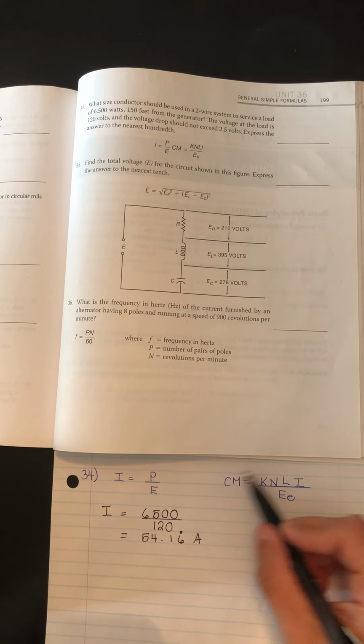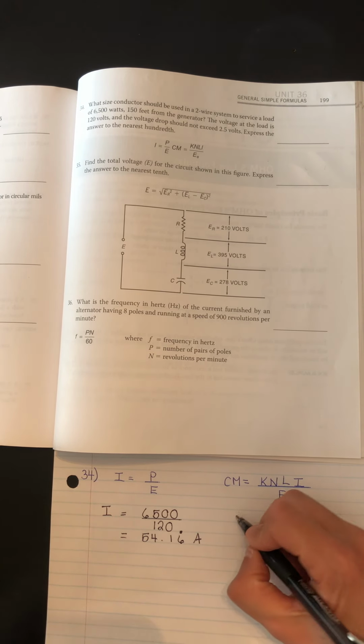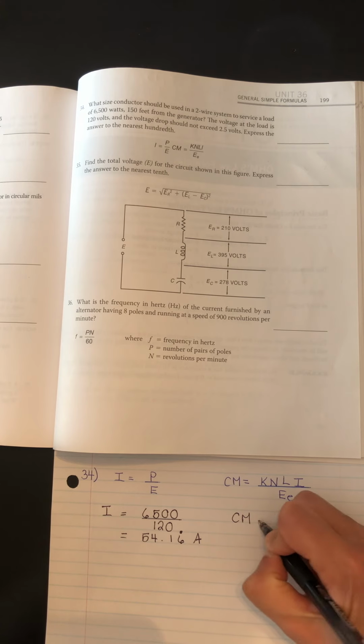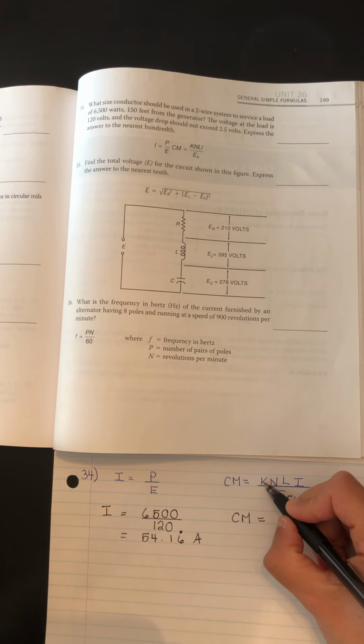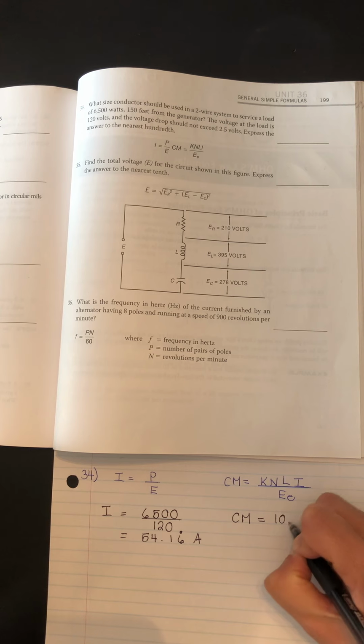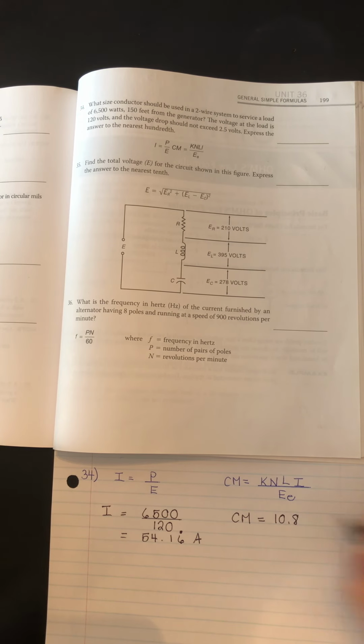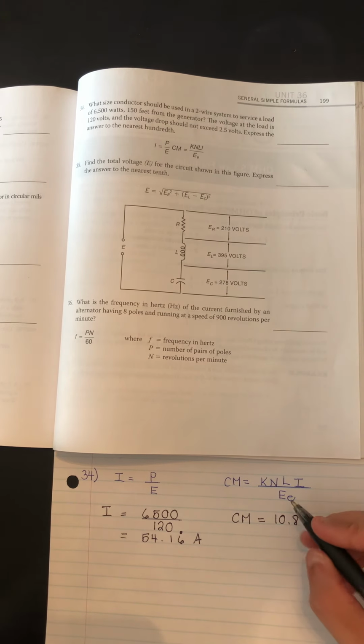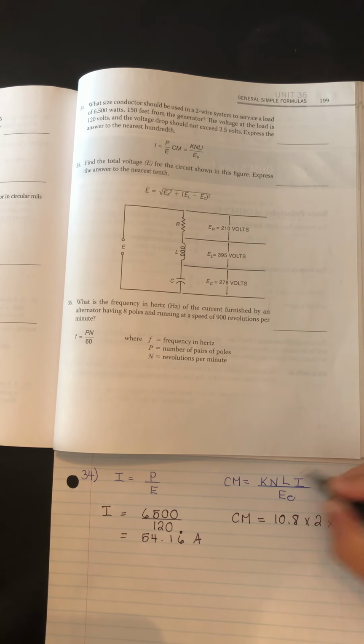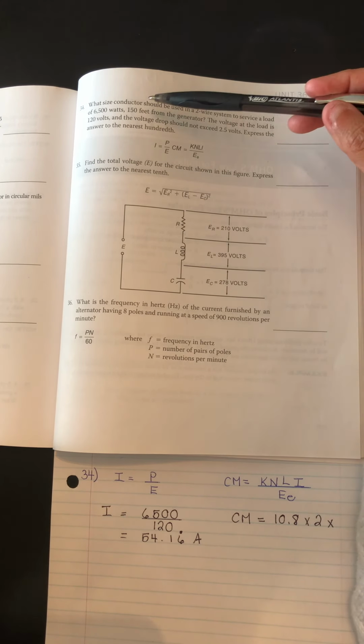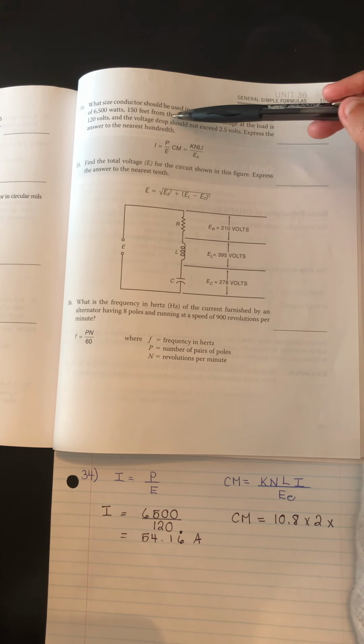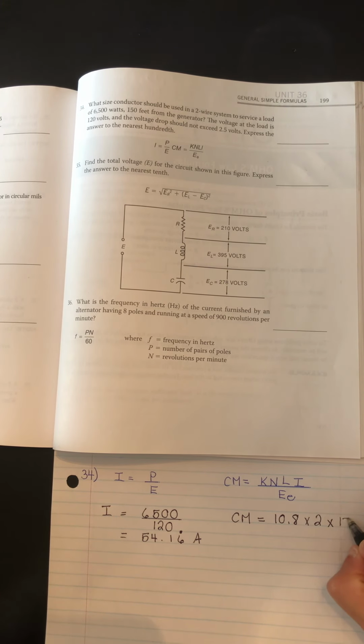And now we can go to our other formula here for cross-sectional area in circular mils. Again, we can substitute 10.8 for the constant associated with copper. N represents the number of wires, and it's a two-wire system. So this is times 2. L is the length of the wire. It's 150 feet from the generator. So that quantity in feet goes here.